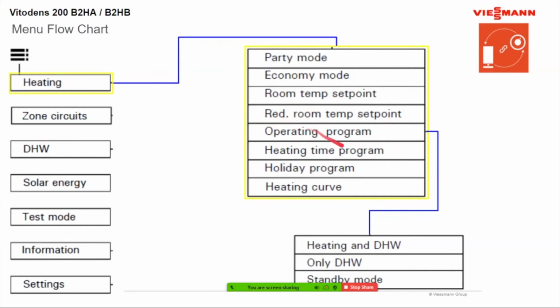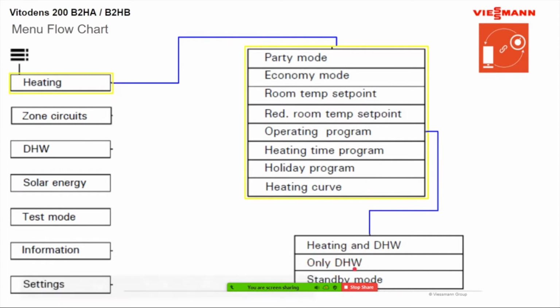And as you can see, you can go with heating and domestic or domestic only. I do have some installations with our boilers in it, and it's only in domestic. Just remember, if you're doing only domestic, it doesn't mean you can have no outdoor sensor. You still have to have the outdoor sensor connected to the boiler. In some situations, I hung it on the wall, knowing that it's not going to get warm enough, but I play around with my room temperature set point, so I know the boiler's not going to fire for a heating curve.